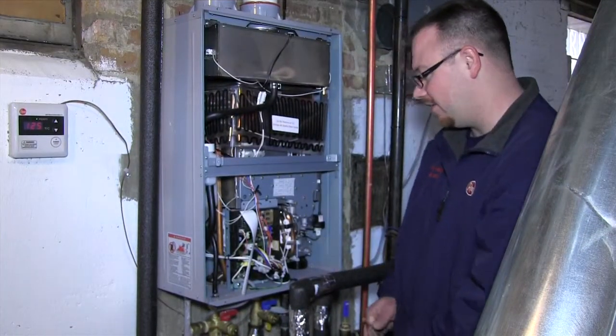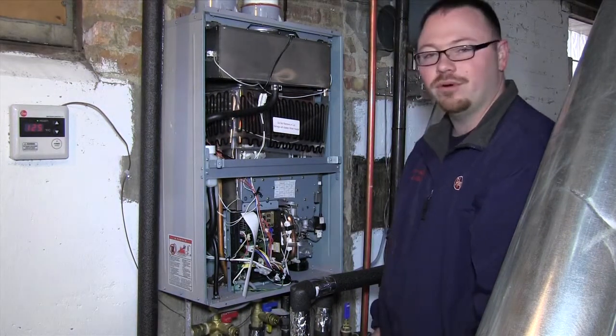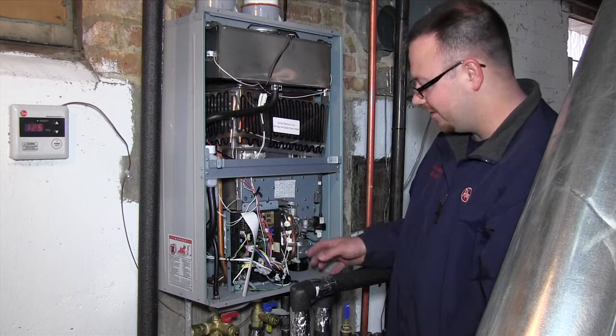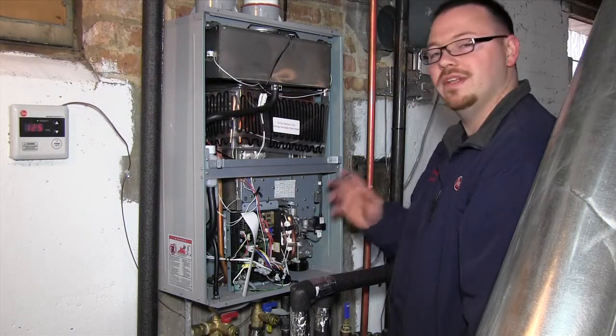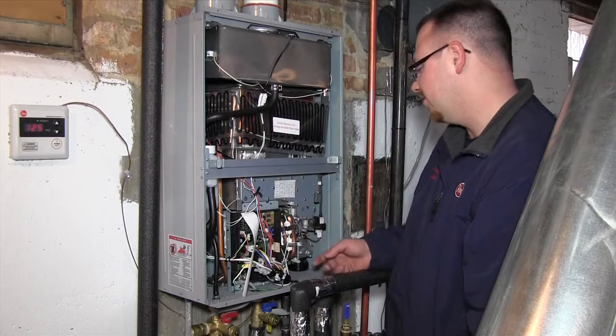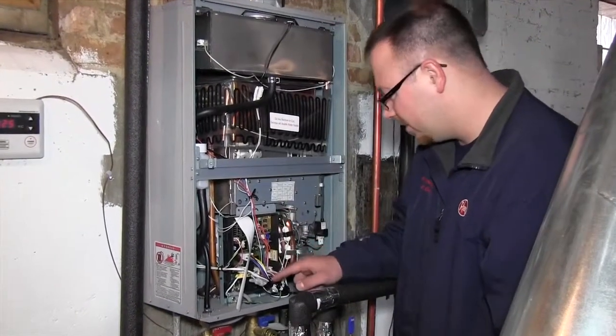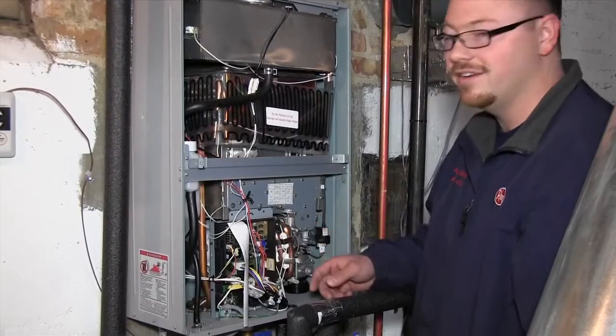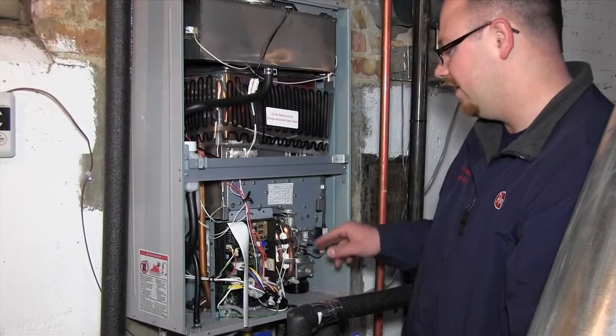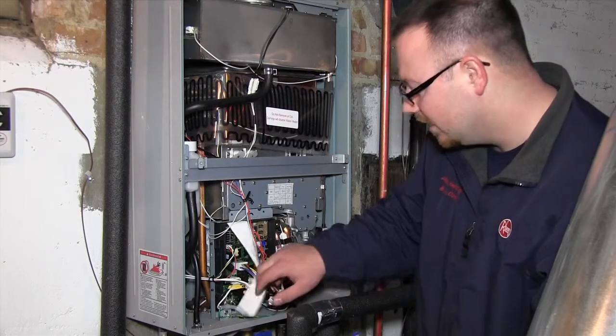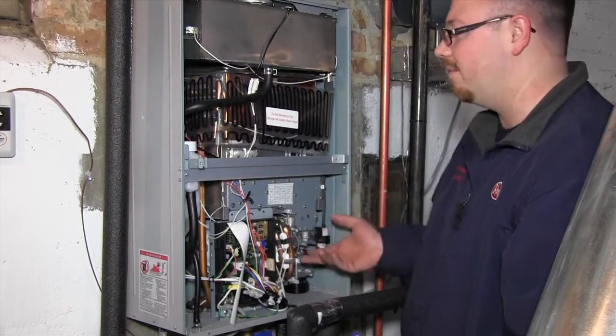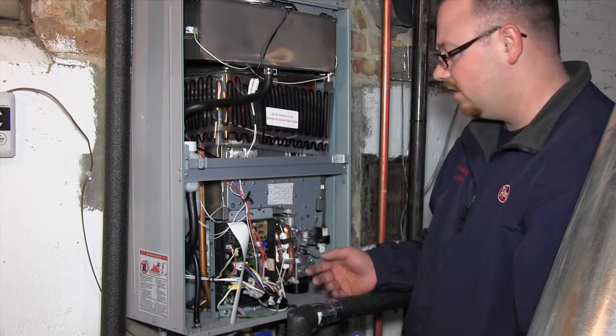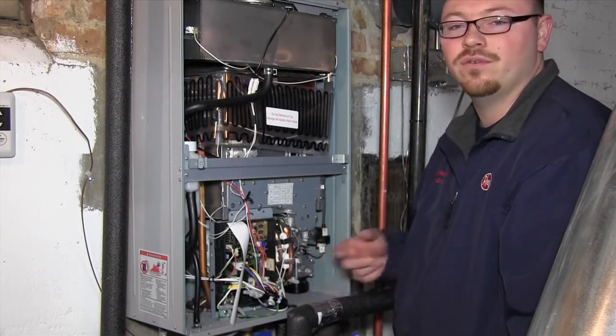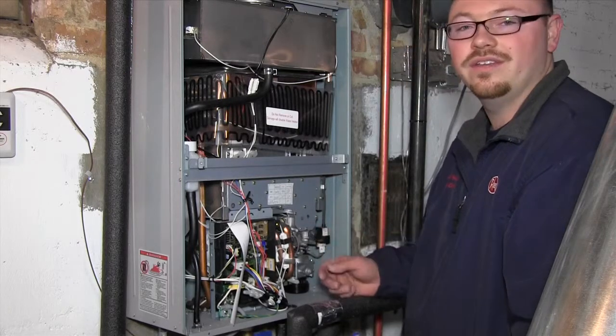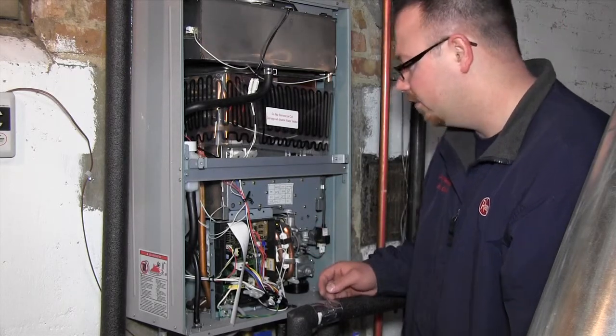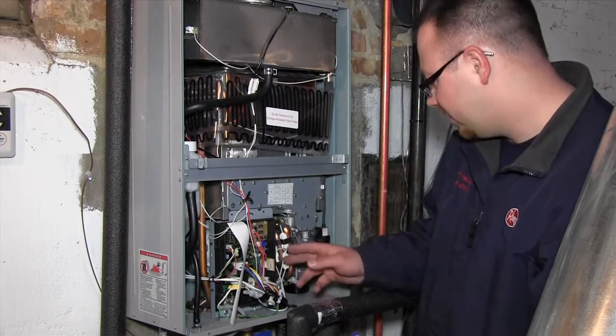Okay, we got the access panel off here. We're going to show you some of the basic components of this. It looks very complicated here. There's a lot of wires and controls. It's actually a very nice, simple design for troubleshooting too. This is the integrated circuit board. This will actually be the brain of this tankless water heater. This puts out all the inputs, all the sensors. It even displays fault codes. So if there was a problem with the tankless water heater, it'll actually tell the circuit board what's going on. So when we come out as the service tech, we can easily find out what's going on and immediately fix the problem.